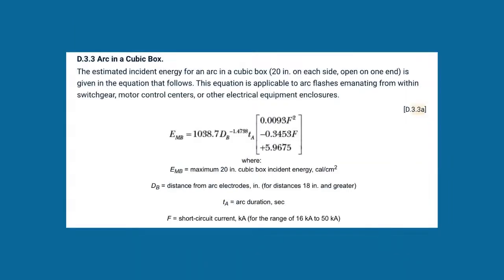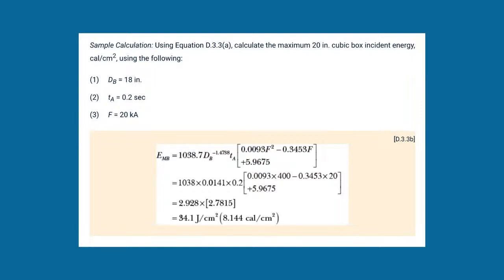Now watch this. I'm going to use the exact same values, plug these into the calculation, and because it's more contained and it can't get out into the free air as quick, now you're going to have at least 8.144 cal. Right. One thing that blew me away when Mike Barr did his open air thing was that they were energizing 80,000 volt switches with 2 cal on. Yeah, but there's a ton of open air up there, and they're energizing from down below. All they're going to get is some little sparks on them.